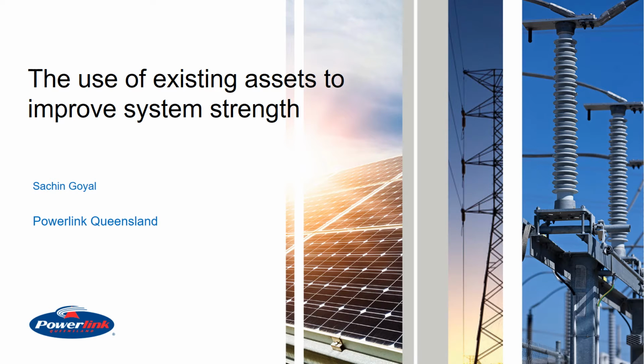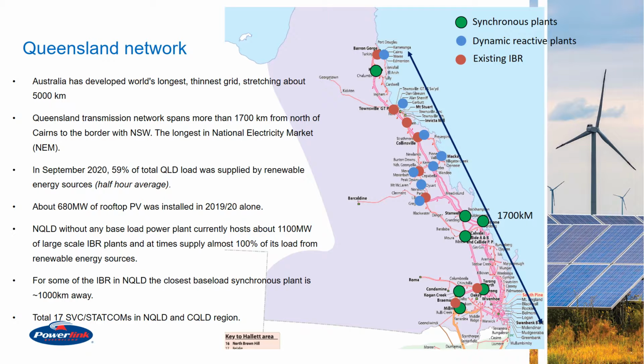In this presentation, I will be sharing some of our experiences with system strength issues that we have had in Queensland and how we have managed to improve the system strength using existing assets such as SVCs and inverter-based renewable resources without actually increasing the fault level. This presentation highlights the fact that system strength is not just the fault level and how rightly tuned IBRs can actually supply the system strength rather than consuming it.